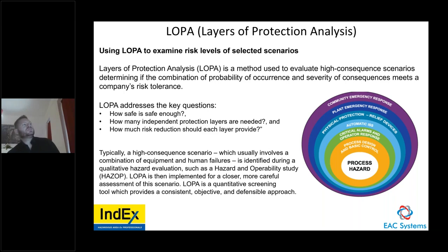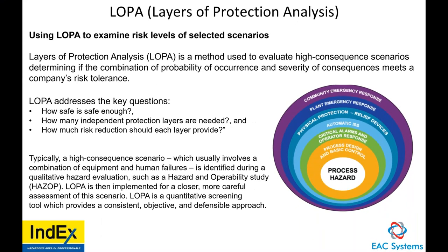When we talk about Layers of Protection Analysis, we're using LOPA to determine the risk levels of selected scenarios. It's a method to evaluate high consequence scenarios, determining if the combination of probability of occurrence and severity meets the company's risk tolerance. The key questions asked are: how safe is safe enough, how many independent layers are needed, and how much risk reduction should each layer provide?